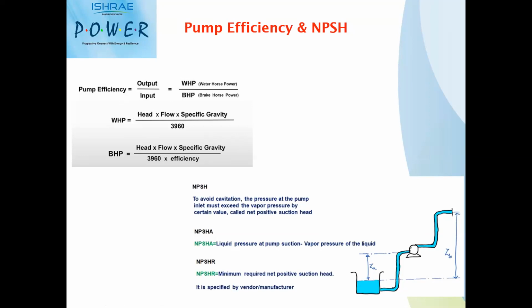So in that case, we have to add the losses in the motor to this calculated hydraulic efficiency, as well as the losses from the VFDs. For example, say my hydraulic efficiency of a pump is around 80%, and I am using an IE3 motor which has an efficiency of 95%. So I'll be adding those losses of 5%. So 80 divided by 0.95 will give me the overall efficiency of the pump. And if it is a VFD driven pump, say I have another 2% losses on the VFDs, so 80 divided by 0.95, again divided by 0.98, gives me the overall input power or overall efficiency of the pump as a whole unit.